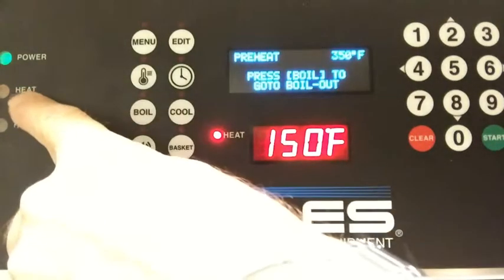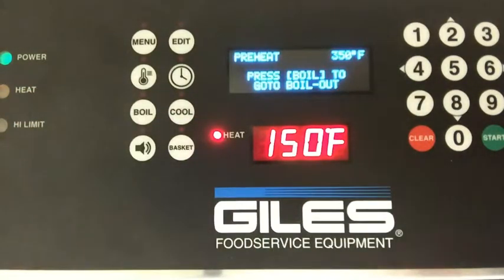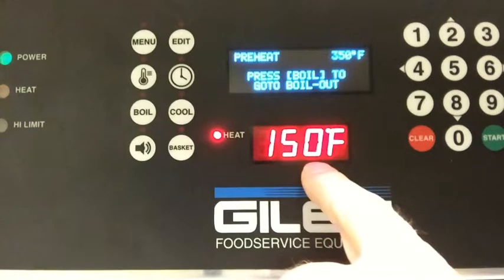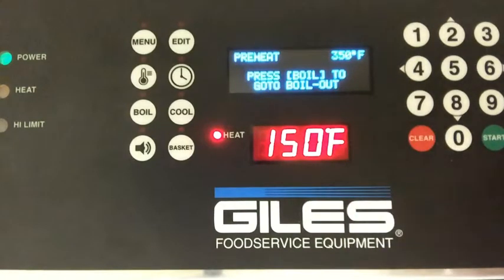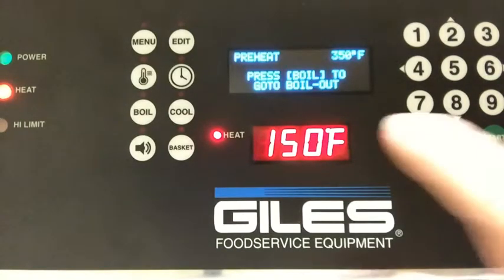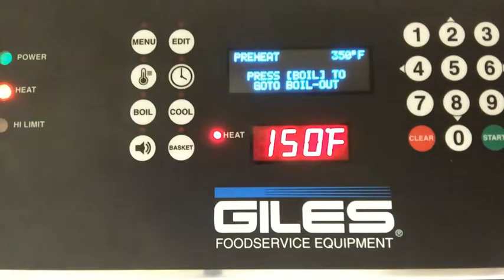Now you'll notice the heat light came on here, but our yellow heat light is still not on. We're at 150 degrees. This is the actual temperature right now. So we're going to go ahead and turn the cook switch on, and when I turn that on, you'll notice now we've applied power to the heat contactor. So this will slowly start to heat up.